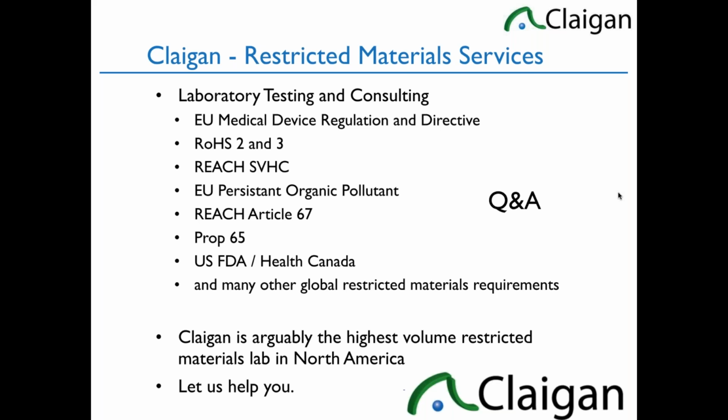There is some engineering evaluation. The material systems are different. We may have to do occasional tests for beryllium when you have a copper electrode in an invasive situation. But we're all structured. If you're doing MDD with us, MDR is not a big stretch. It would take some work, but not really retesting of any significance to convert over to MDR. It's part of, again, as I mentioned before, when you're doing one of these restricted materials compliance requirements, if you're doing it properly, you should be able to structure it so that you can leverage it or make variations in your process to handle the others.